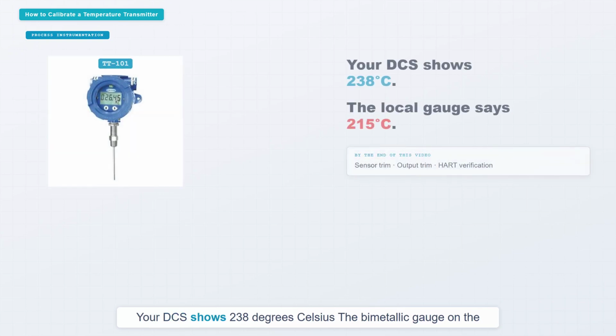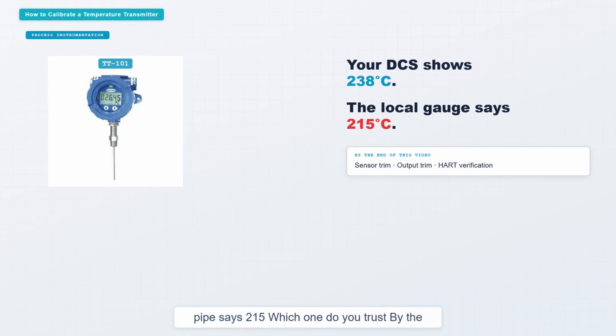Your DCS shows 238 degrees Celsius. The bimetallic gauge on the pipe says 215. Which one do you trust? By the end of this video, you will know exactly how to calibrate a temperature transmitter, sensor trim, output trim, and HART verification, so your DCS values stay accurate.